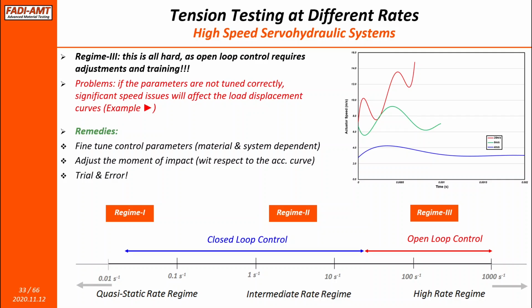One problem is basically the speed itself. This is open loop, and this is usually fast testing or high speed testing, which means the parameters of how you perform the test. And let me focus on one particular item here. This is in regards to at what speed and in what kind of acceleration profile do you impact your sample.